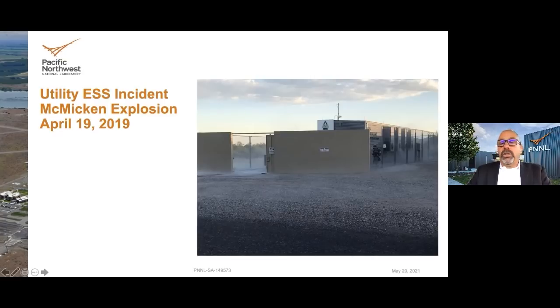This incident occurred at a utility substation in Arizona in April of 2019, and it was reported by somebody driving by. The actual smoke alarm inside that triggered the clean agent discharge was not reported to the fire department by the monitoring center, so there was a significant delay.